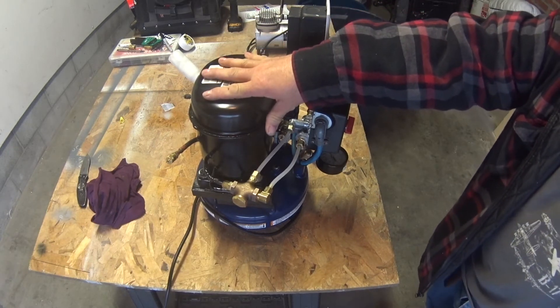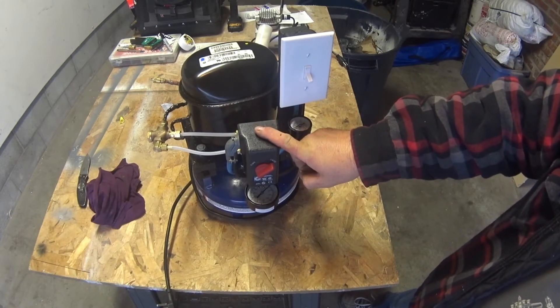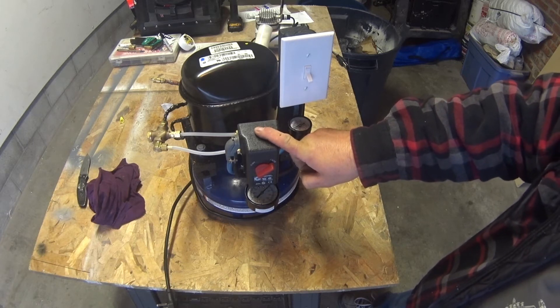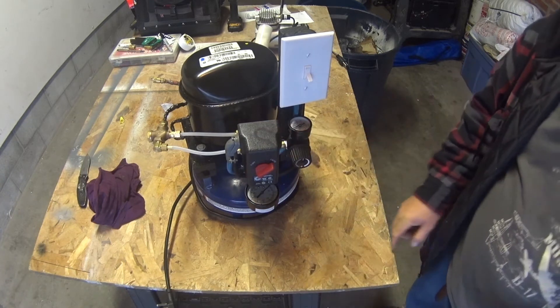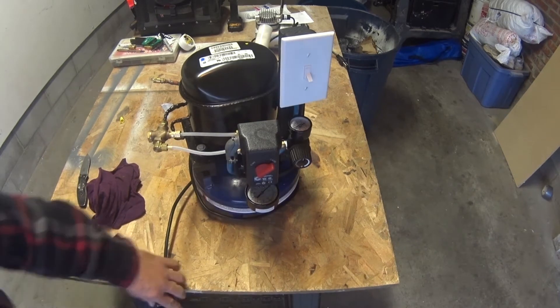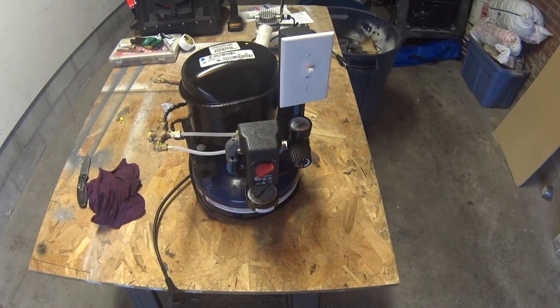When the compressor hits the correct pressure and shuts off, this unloader valve releases the pressure for the compressor so next time it starts up there's no load on it. And this check valve stops pressure from going back to the compressor. Here is my pressure gauge — I have it set to come on at 75 psi and shut off at 110. This is what it will sound like — I'll flip the power switch on. It's pretty quiet, isn't it? It's going to be great for the back room — it won't wake anybody up.